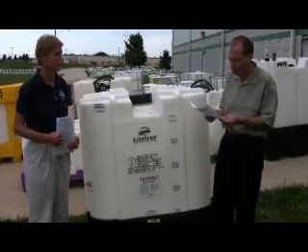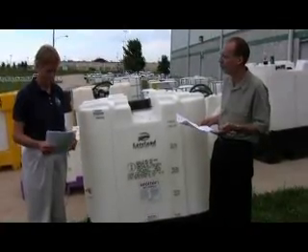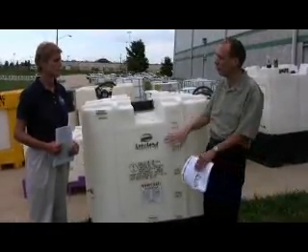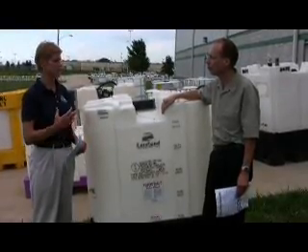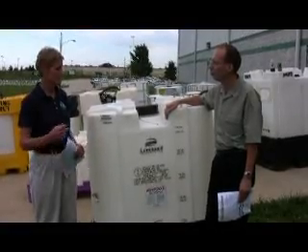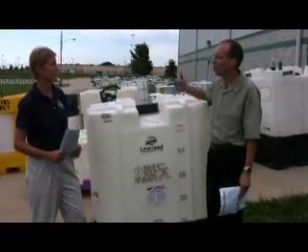All right, we also have a second part of this question that says, if not marked, the manufacturer has verified it meets at least US DOT Packing Group 3. So we could have some containers that meet the specifications but don't have the markings on them. Is that right? That's right. When we referred to and adopted the DOT regulations, they do allow certain containers, portable containers, that don't need this marking on it.